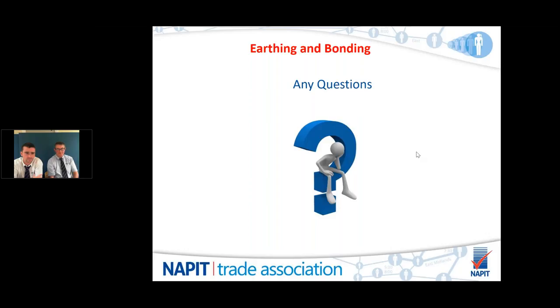No, really. I suppose in the event that the Ze is high, you could install a rod, make a TT system to inform the supply authority. That way you're covering all angles. I'm guessing that's maybe where the question was going. But yeah, notify the supply authority that they'll come out at some point if required. But until that time, you could knock an earth rod in to meet requirements.